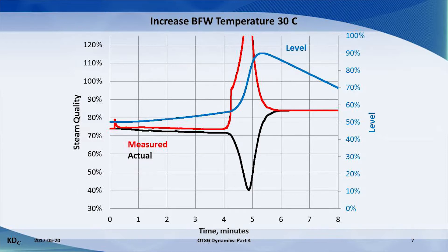For the first four minutes, there is no impact to the steam quality because the change in temperature has not yet impacted the liquid holdup. Then the actual quality, the black line, dips low when the extra water is kicked out. The measured venturi quality, the red line, spikes high with the extra water and reads over 100%. Then everything settles out. This sudden change takes place over about a minute.